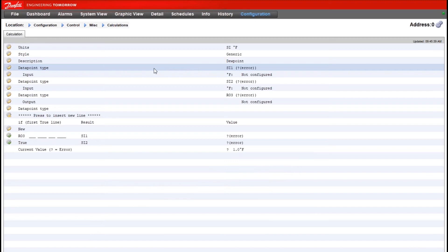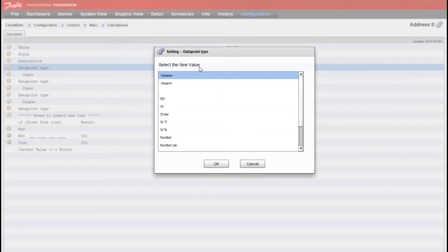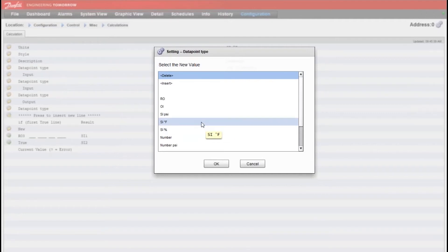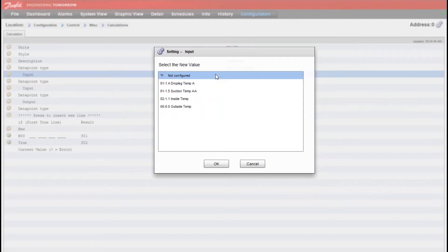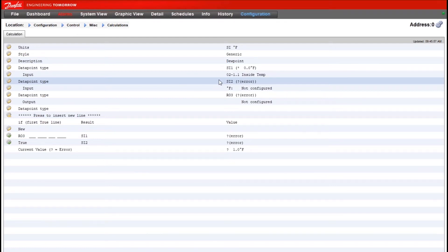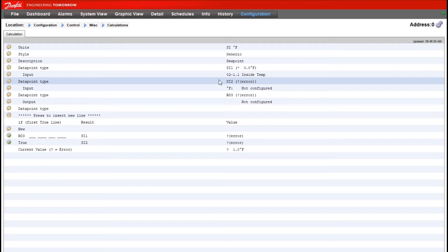So for an indoor humidity example, our first data point type—we'll make sure we're selecting SI degrees Fahrenheit here. This will allow us to choose temp sensor. I'll use the generic indoor temp sensor that the System Manager offers. This could be any temp sensor from a rooftop unit, depending on how you want to configure this, or something else completely different on the refrigeration side for anti-sweat heaters.